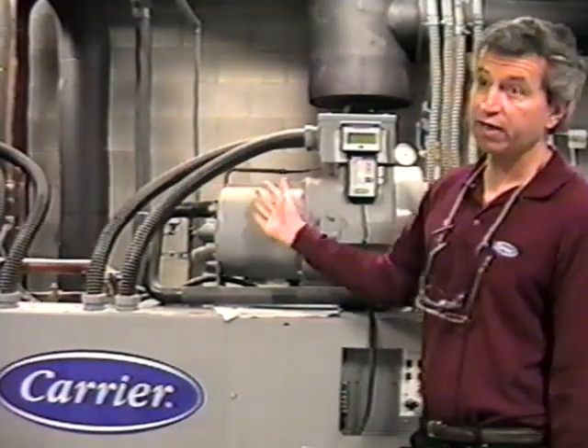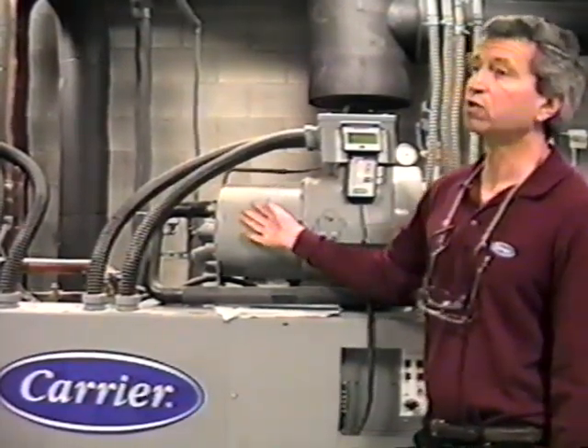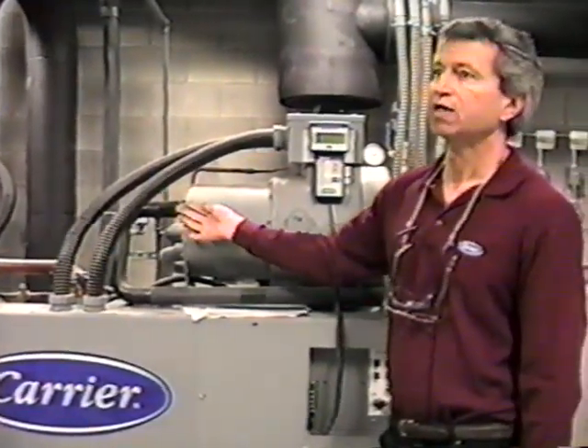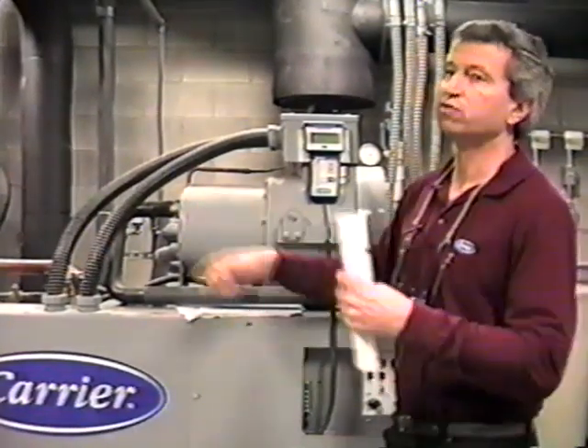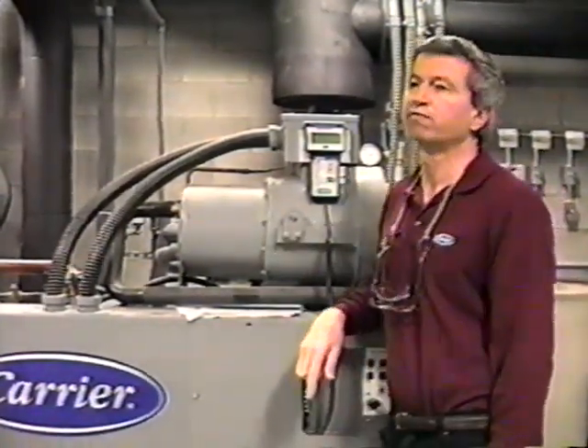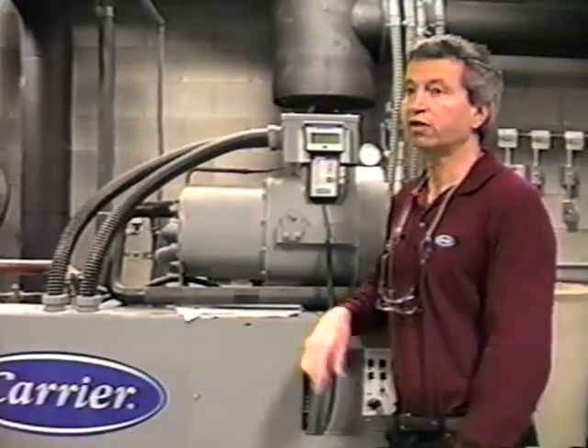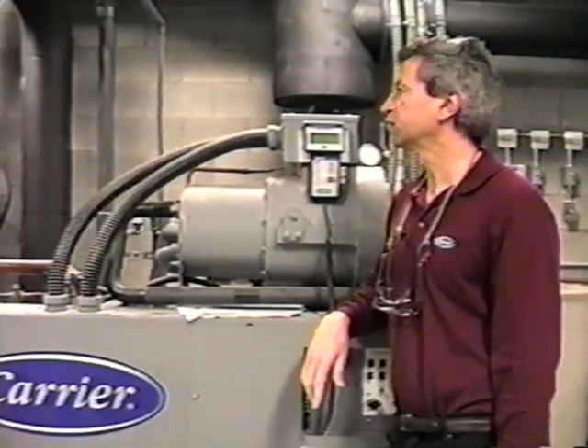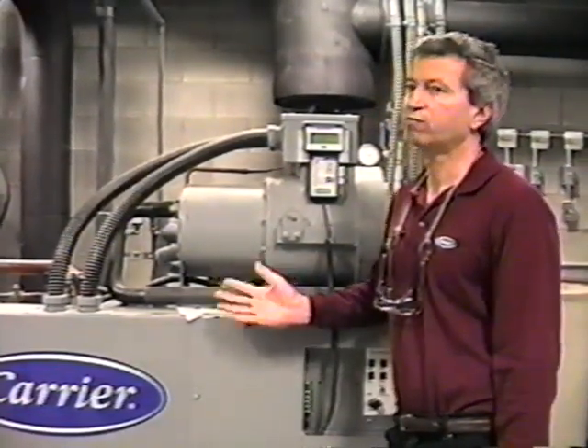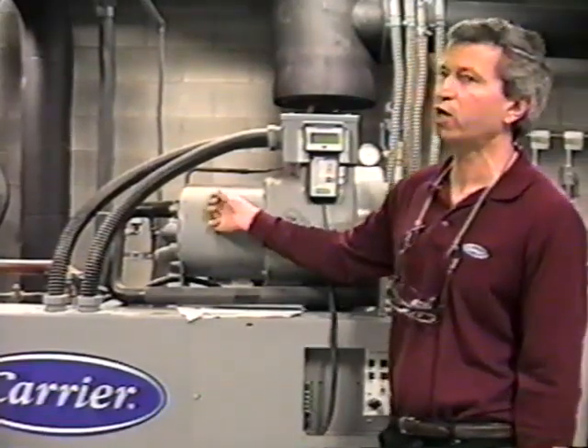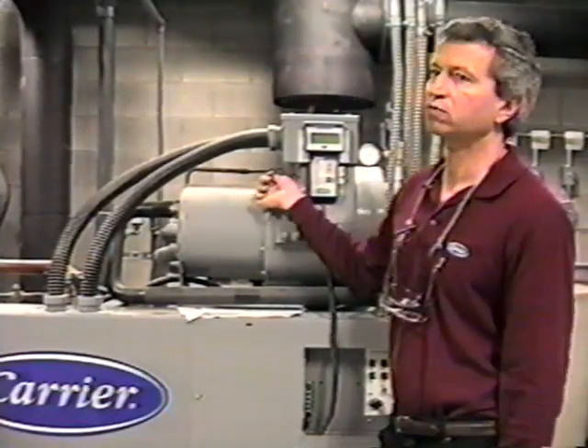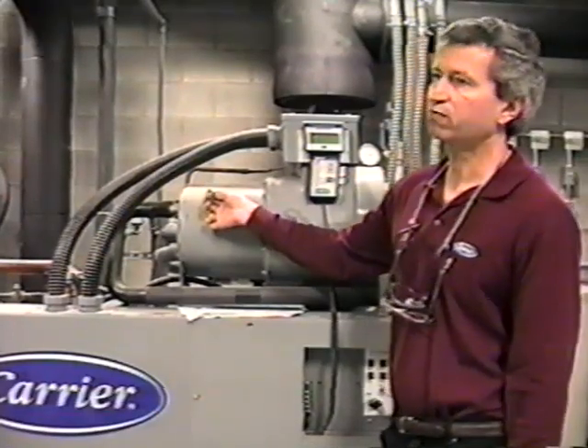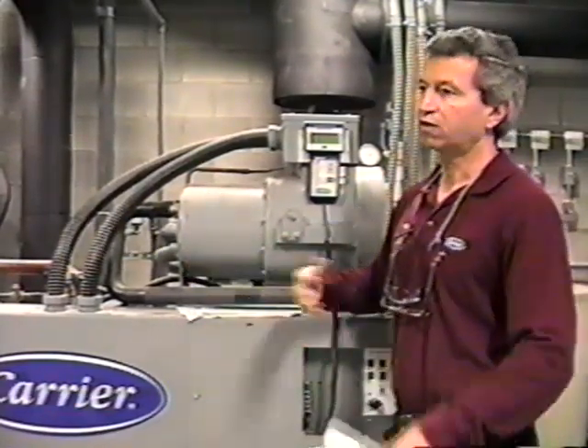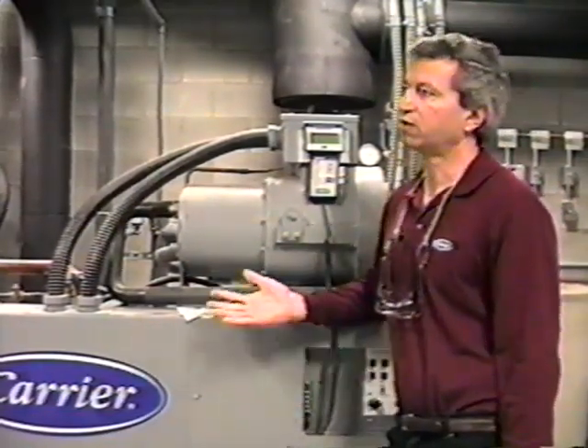The compressors look identical, physically they look identical, but internally they have a different size motor and a different size set of gears. The rotors of the screw are turned with a gear drive. And again, depending on the capacity required from that compressor will determine which motor is put on here and which set of gears. So the larger compressor obviously is going to have a little larger motor and also turn a little faster to provide the capacity required.